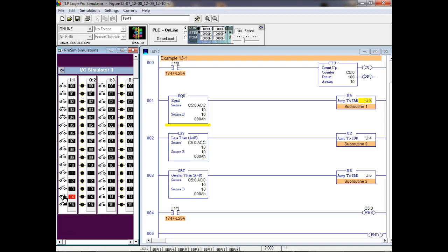But all we're trying to illustrate is that if you need an output in a certain state when you come out of that subroutine, then you gotta put it in that state when you come out, right? Especially a conditional subroutine. If it's unconditional, it's gonna run all the time anyway. If it's conditional, whatever state your outputs were in when you came out of the subroutine, they're gonna stay in that state until that subroutine does what? Runs again. And this one doesn't run them again. Once it's through with them, it's through with them.